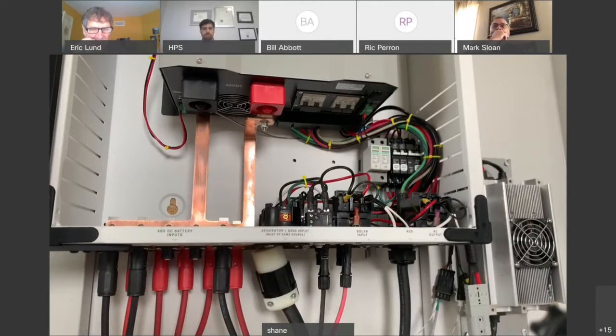You're not pulling. So you have to keep that in mind when you're sizing your generator or when you're choosing your charge current, so you don't bog down your generator. Typically, I like to save 50% of my generator capacity for the load in the home.